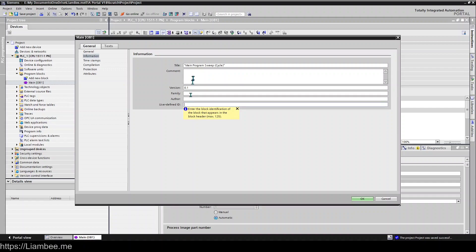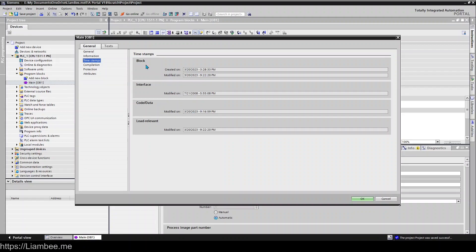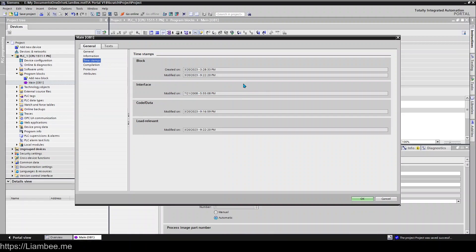Timestamps are useful because this is how TIA Portal actually checks whether something's changed in your project. So timestamps are one of the things that is checked between an online project and an offline project. So between the PLC and your offline project, if the block has changed its modified dates or the interface or the code or data, you're going to get a comparison error saying that the one on the PLC is either newer than the one in the project or the one in the project is newer than the one on the PLC.